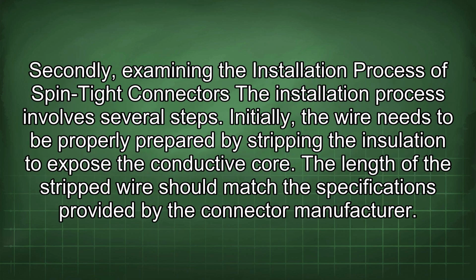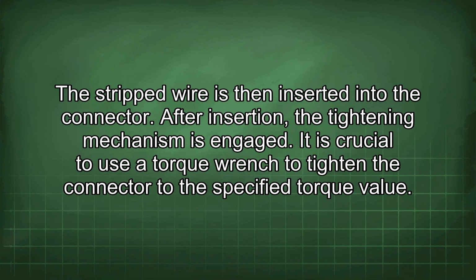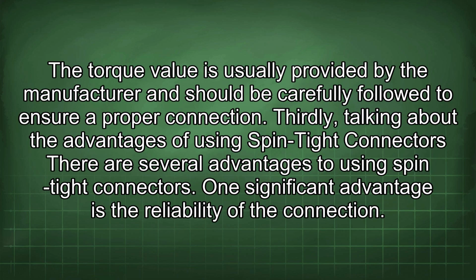Secondly, examining the installation process of spin-tight connectors. The installation process involves several steps. Initially, the wire needs to be properly prepared by stripping the insulation to expose the conductive core. The length of the stripped wire should match the specifications provided by the connector manufacturer. The stripped wire is then inserted into the connector. After insertion, the tightening mechanism is engaged. It is crucial to use a torque wrench to tighten the connector to the specified torque value. The torque value is usually provided by the manufacturer and should be carefully followed to ensure a proper connection.